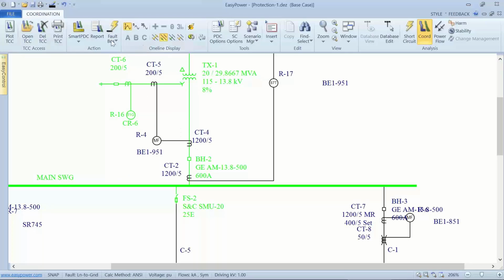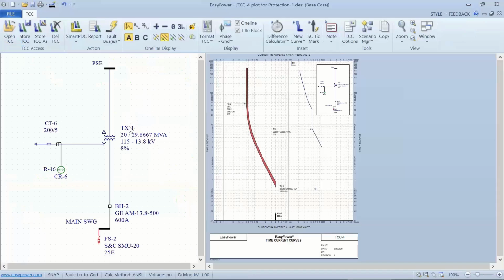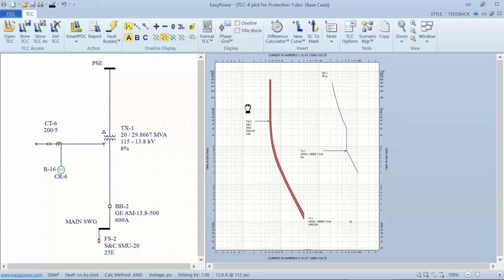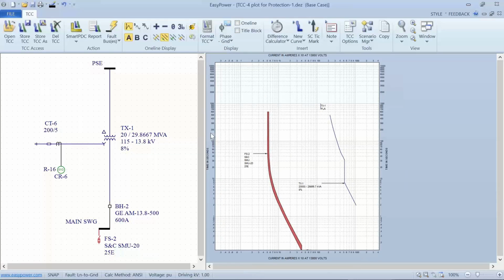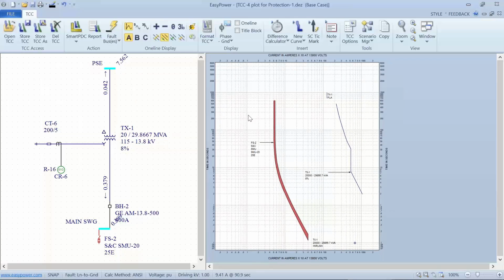It should get us there. Now, as I mentioned, this is a little tricky in terms of trying to do this live, because sometimes you need to take a little bit more time looking for the specifics. But if we fault all the buses, we get our 300 amp.